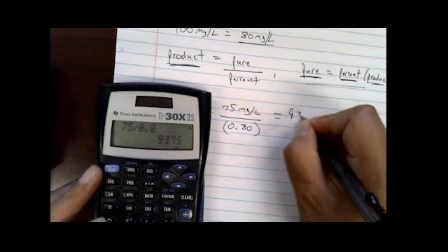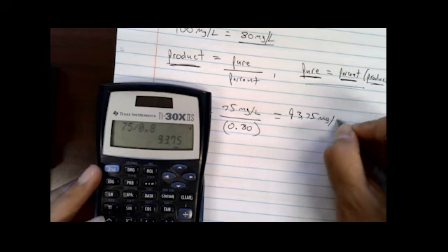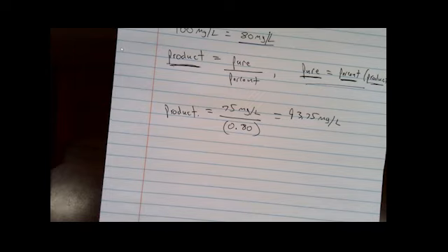That is 93.75 milligrams per liter of soda ash, right? That, rounded up, is equal to 94 milligrams per liter. And that's our answer. So this one's more of a basic concept of percentage, of knowing the difference between what amount is the pure, the percentage of the product, and doing a basic multiplication or division of that percentage to find either the pure or the product, in this case the product, which was 94 milligrams per liter. Now let's take a look at the next one.